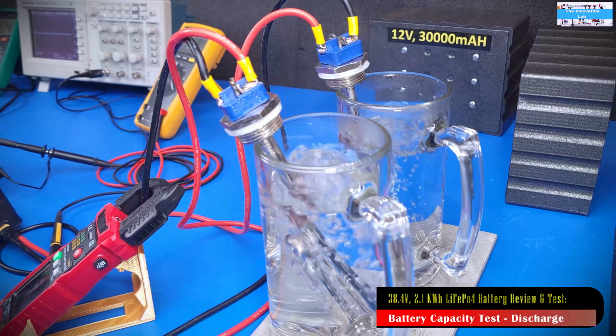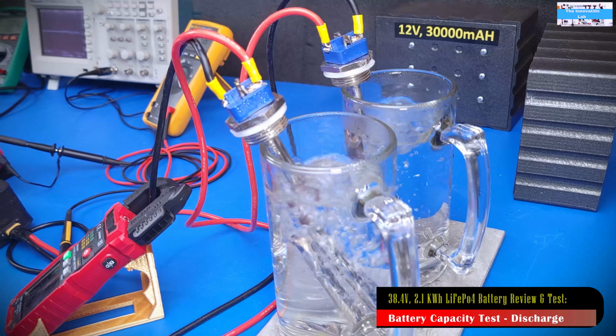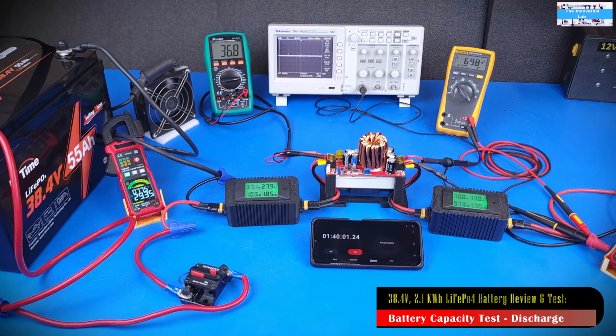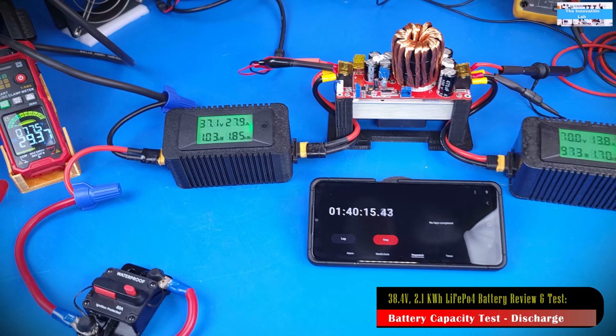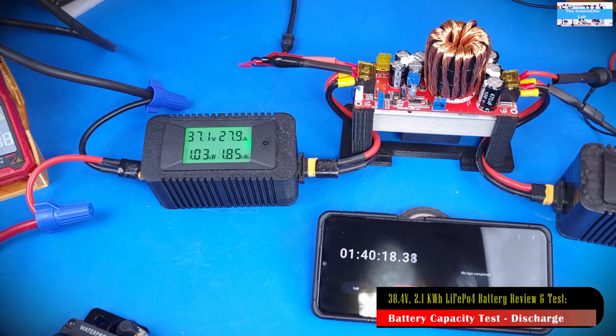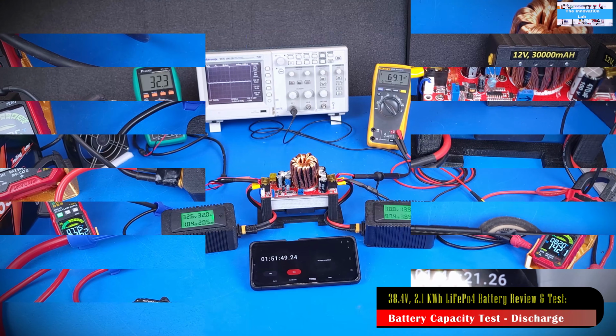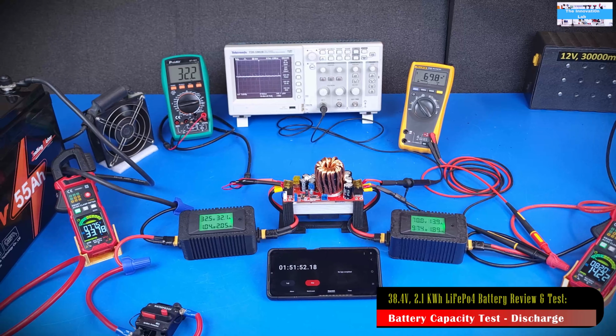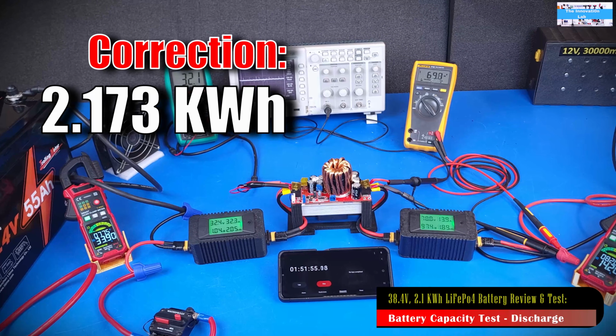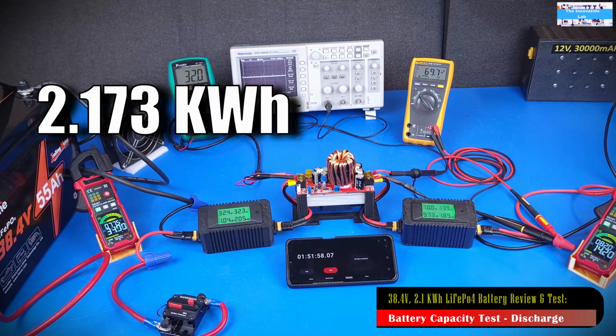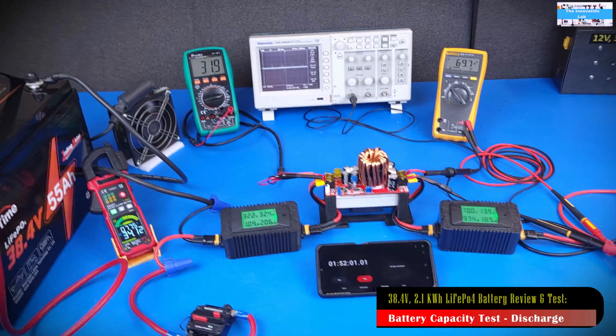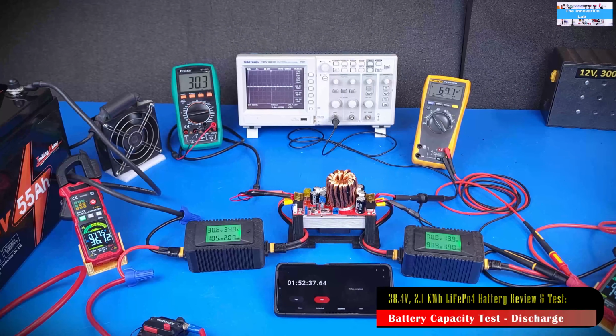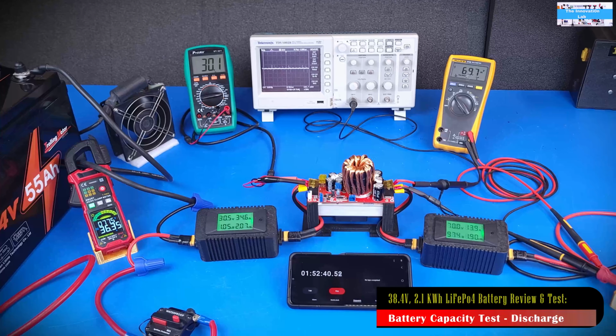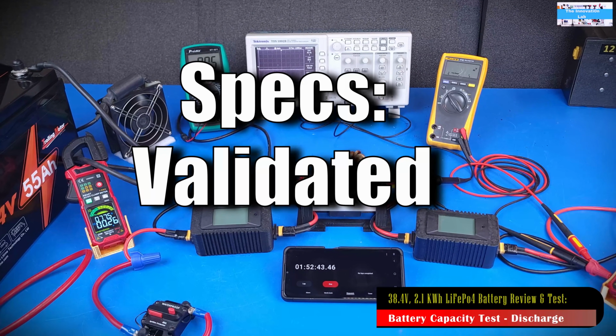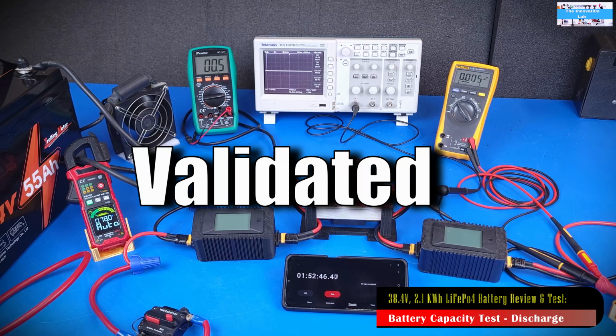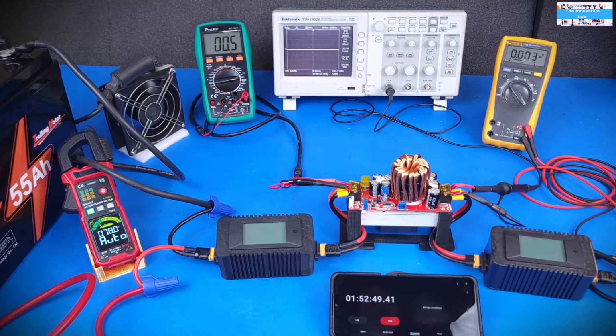Overall I am very happy with the discharge performance of this battery. It was able to provide 1000 watts of steady state power to our discharge load, and that's amazing. Looking at our digital power monitor, this battery system delivered a total of 2.173 kilowatt hours of energy to our test load, doing so while delivering a steady state power of 1000 watts for 2 hours. If you ask me, this is quite impressive, and it validates that this battery system lives up to every single spec the manufacturer has rated it for.